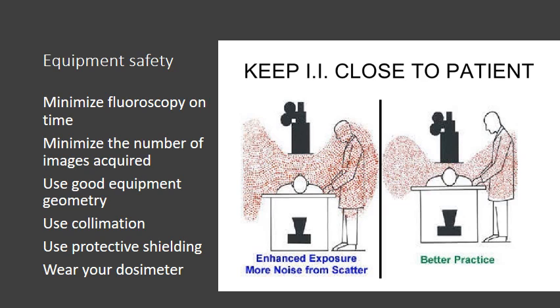The dose mode mentioned earlier allows a technologist to choose between high, medium, and low doses. The normal mode is naturally the most chosen one because it delivers the average exposure needed to keep good image quality. High dose mode is also known as boost mode, and it's needed to visualize low contrast areas that require details to be seen, such as when using small catheters in vascular imaging.